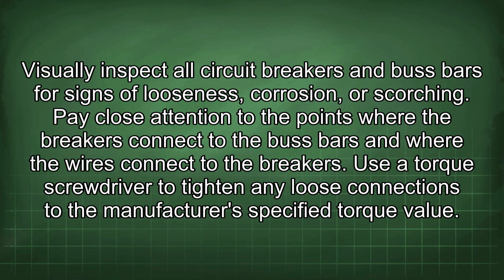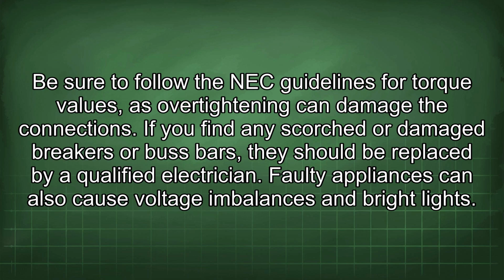Visually inspect all circuit breakers and bus bars for signs of looseness, corrosion, or scorching. Pay close attention to the points where the breakers connect to the bus bars and where the wires connect to the breakers. Use a torque screwdriver to tighten any loose connections to the manufacturer's specified torque value. Be sure to follow the NEC guidelines for torque values, as over-tightening can damage the connections. If you find any scorched or damaged breakers or bus bars, they should be replaced by a qualified electrician.